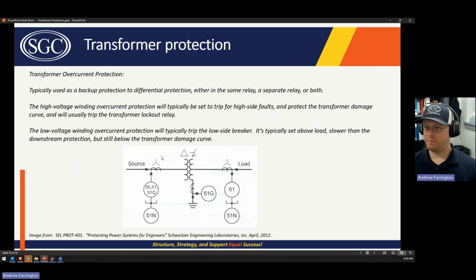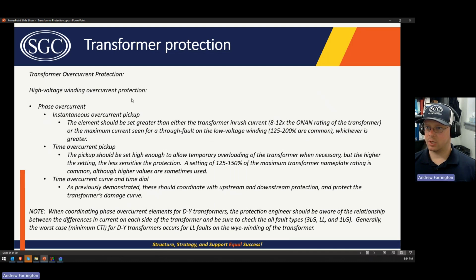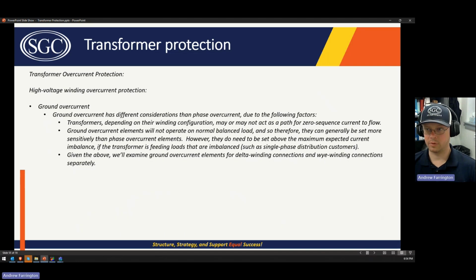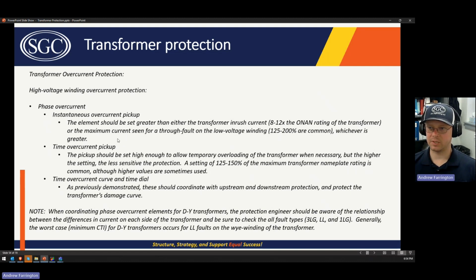The way I've broken this up is high voltage winding overcurrent protection and phase, and then also for ground. And the ground overcurrent protection is dependent upon the winding that's connected. And if that's not obvious to you right now, hopefully it will be as I go through this. So for your phase instantaneous overcurrent pickup for the high voltage winding, the element should be set greater than either the transformer inrush, which is typically estimated to be 8 to 12 times, as a worst case, the ONAN rating of the transformer, or the maximum current seen for a through fault on the low voltage winding of the transformer.